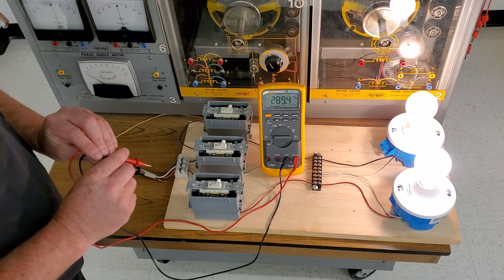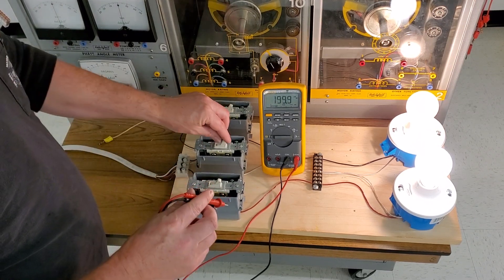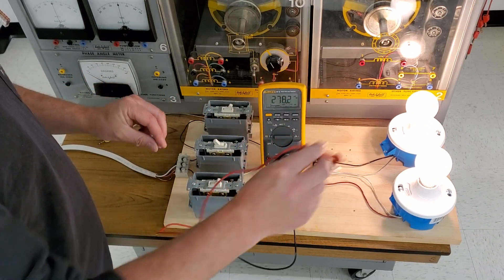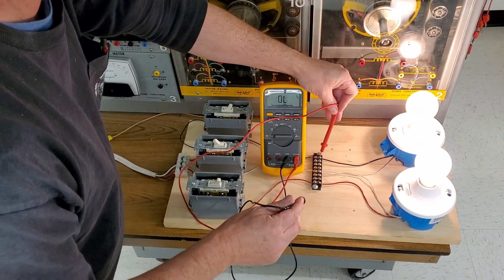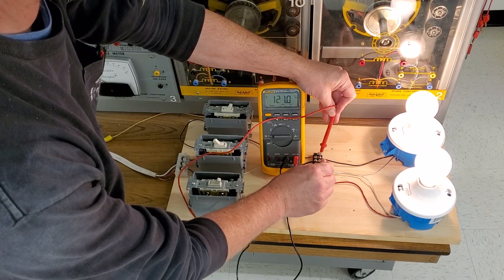What happens if we lose the neutral? Then essentially we put these two light bulbs in series with each other. And you'll notice that from hot to neutral with this bulb, because we are slightly less resistance on this bulb, we're reading 120 volts.